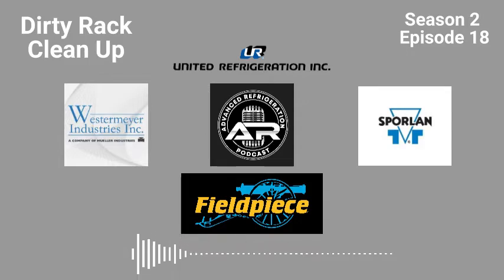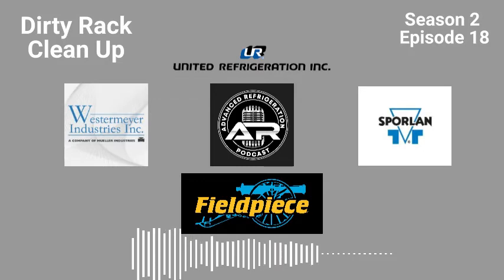Go ahead, Brett. And also seeing what you're seeing as you're opening that up, right? If you see black carbony stuff, that's going to indicate one thing, right? If you go to clean out the screen, you think it's just dirt, but it ends up sticking there where you actually legitimately have to use some kind of contact cleaner. That's indicative of wax, and wax is usually indicative of moisture, right?